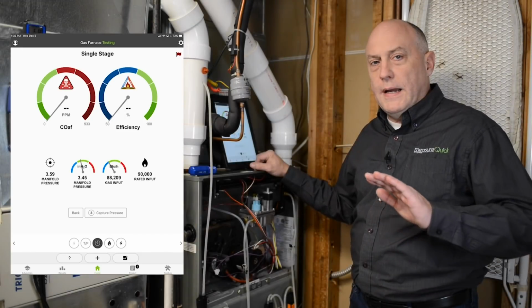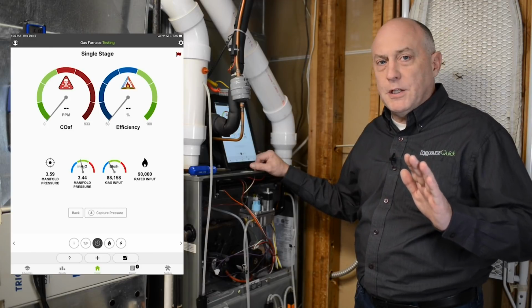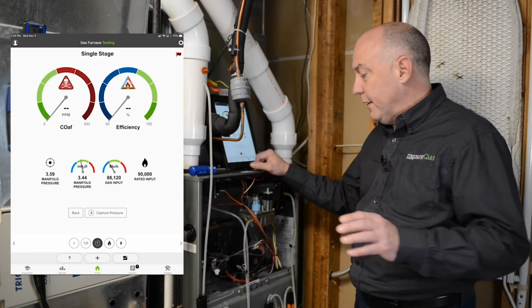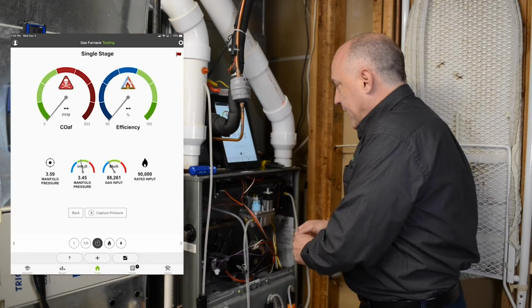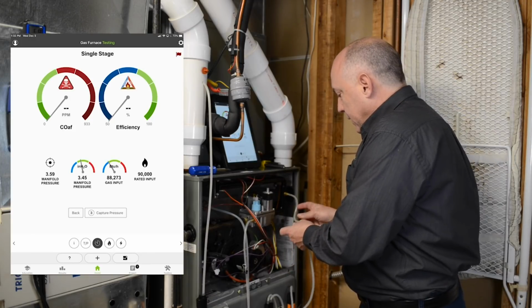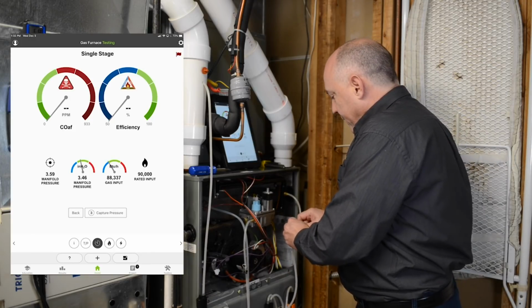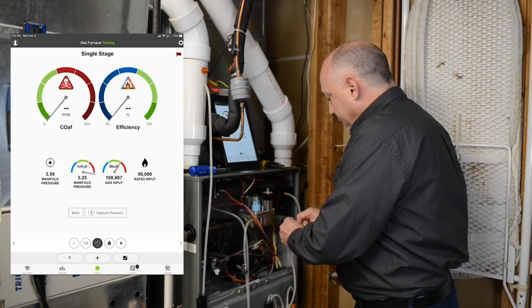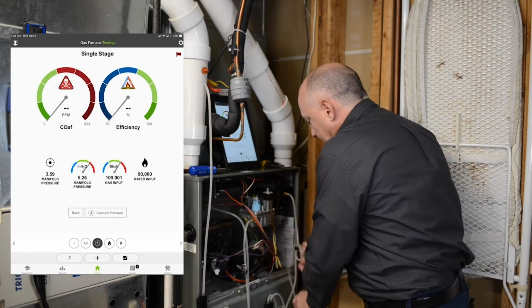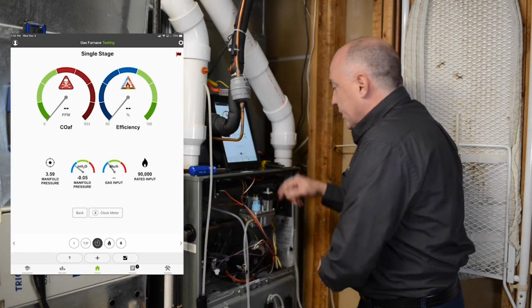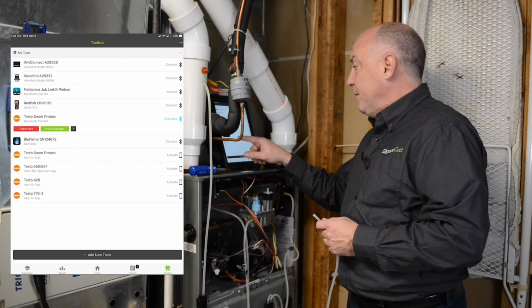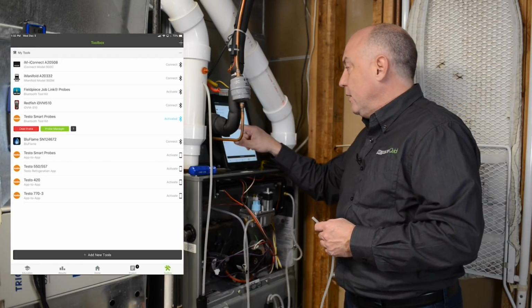All right, so we captured the pressure when we first started. We went out and clocked the meter here. Real quick, I'm just going to make sure that my manometer's still zeroed. So I'm going to valve this off for just a second on my manifold pressure, pull my manometer hose off here, and go into the toolbox and re-zero it, just to make sure that we're zeroed accurately.